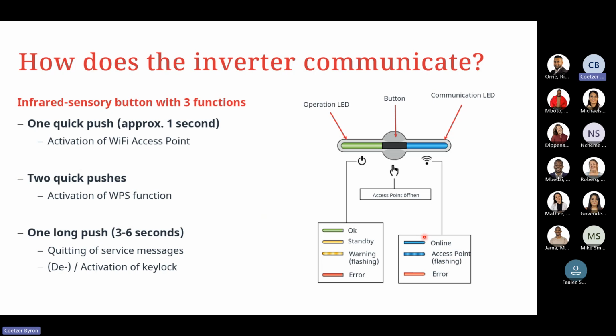So again, how does the inverter communicate? Like I mentioned, with the Pilot devices, we've stepped away from using an LCD screen to notify us of any errors. Instead we're using LED status. If the unit is solid blue, that means the unit is online and operational, and it is online and communicating 100% to the cloud itself. If it is yellow, it's in a standby mode. Yellow flashing is a warning, and red is a simple error that's located on the unit. So again, solid blue means the unit is 100% communicating, so we don't have to stress on site.